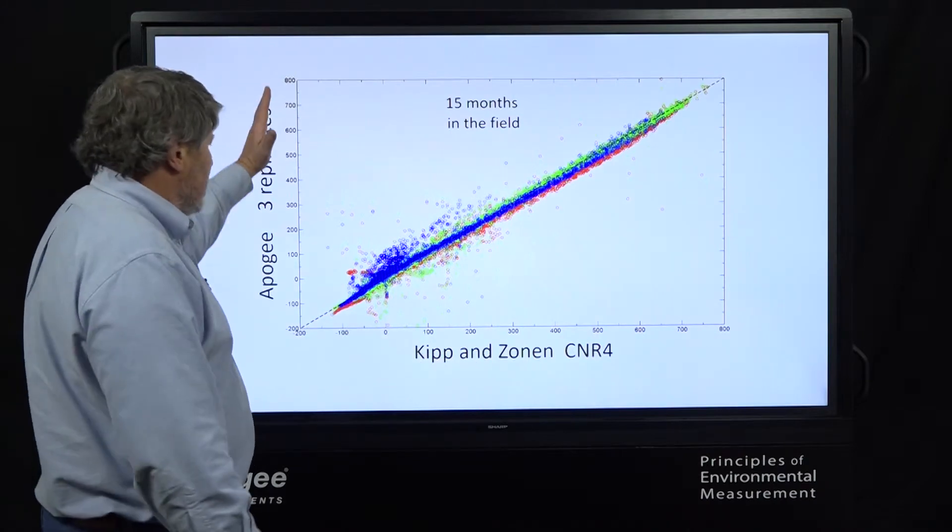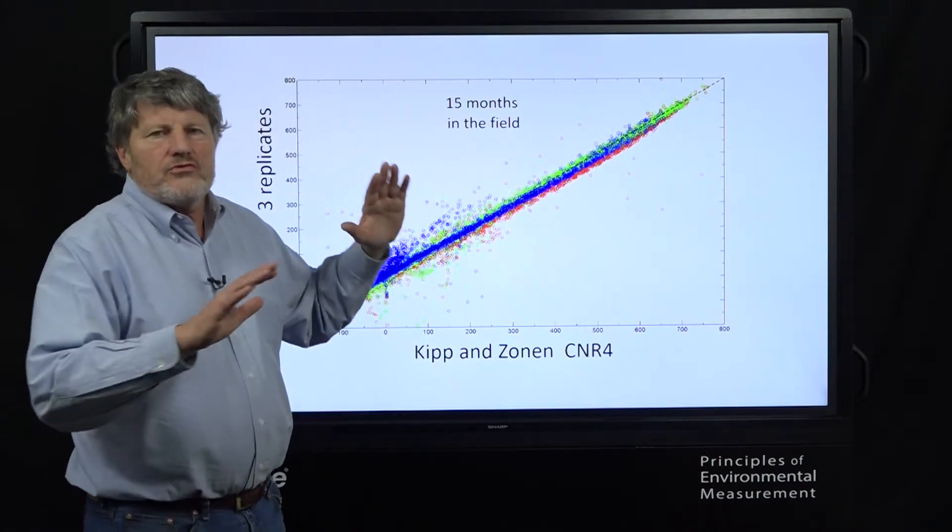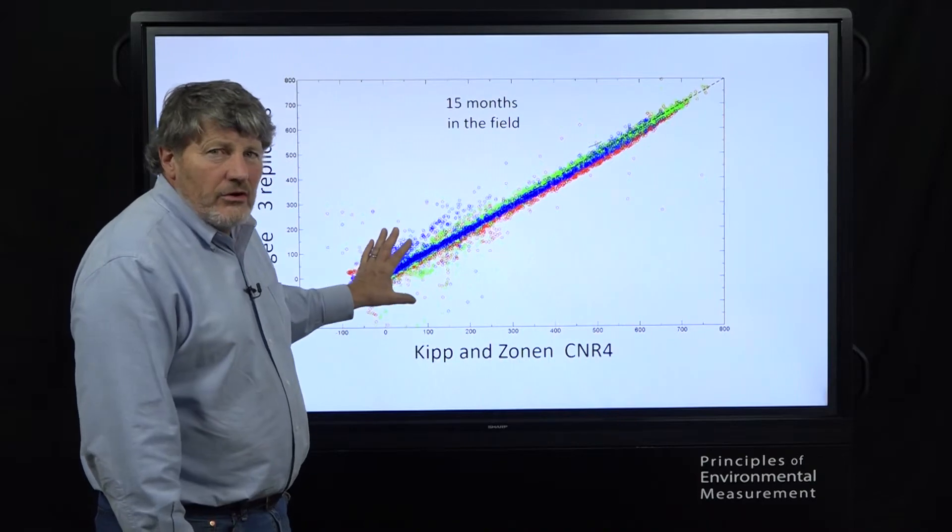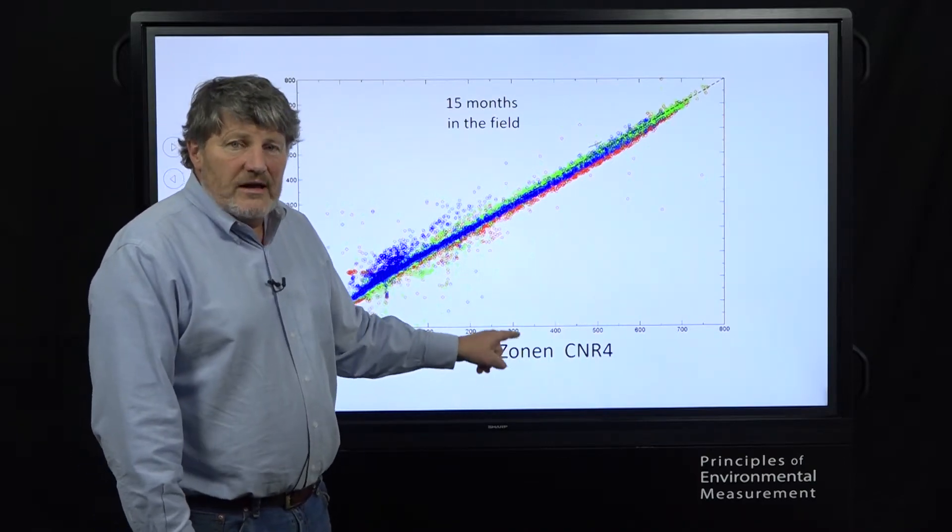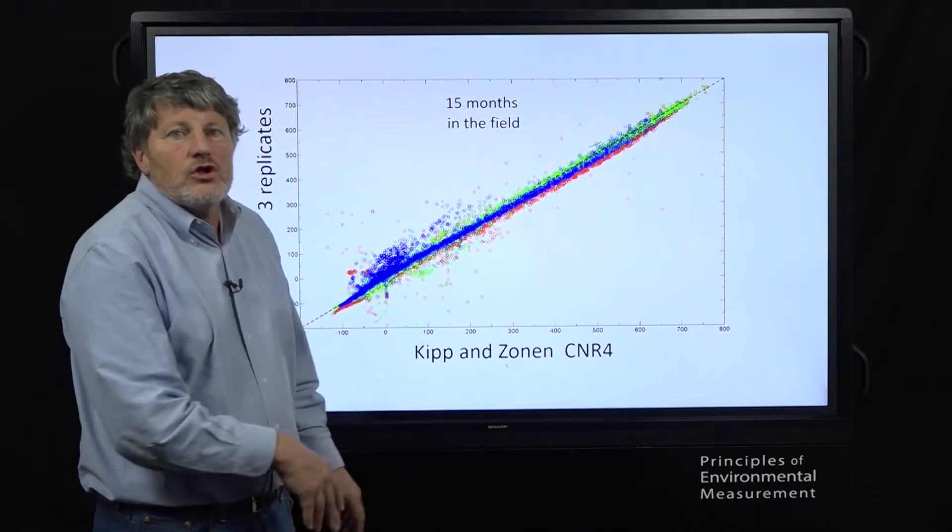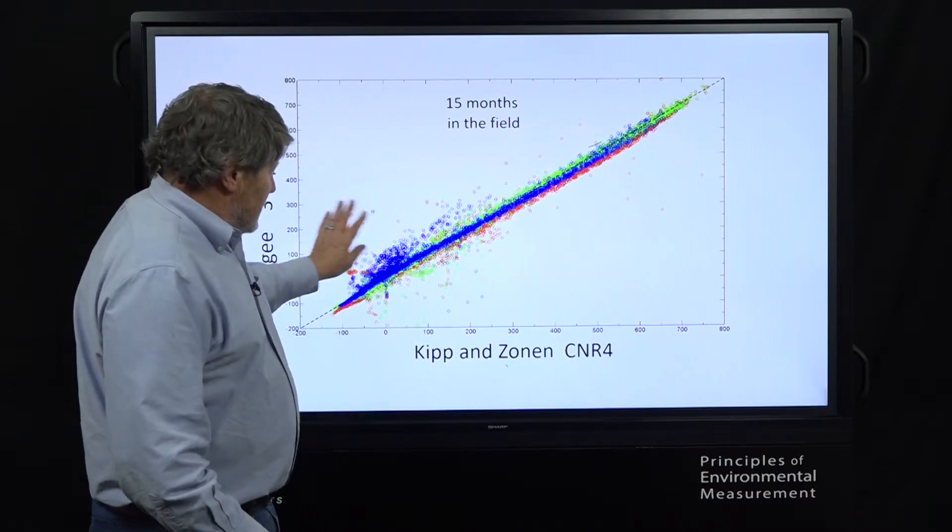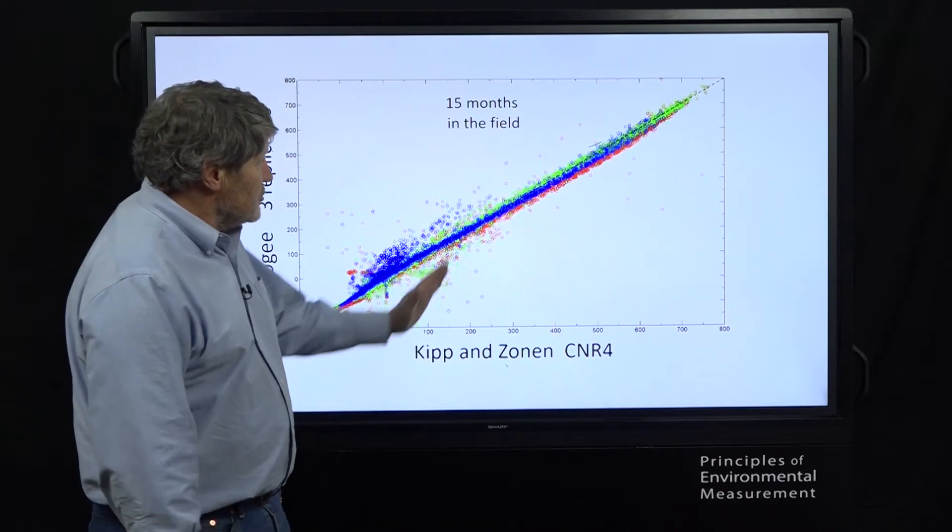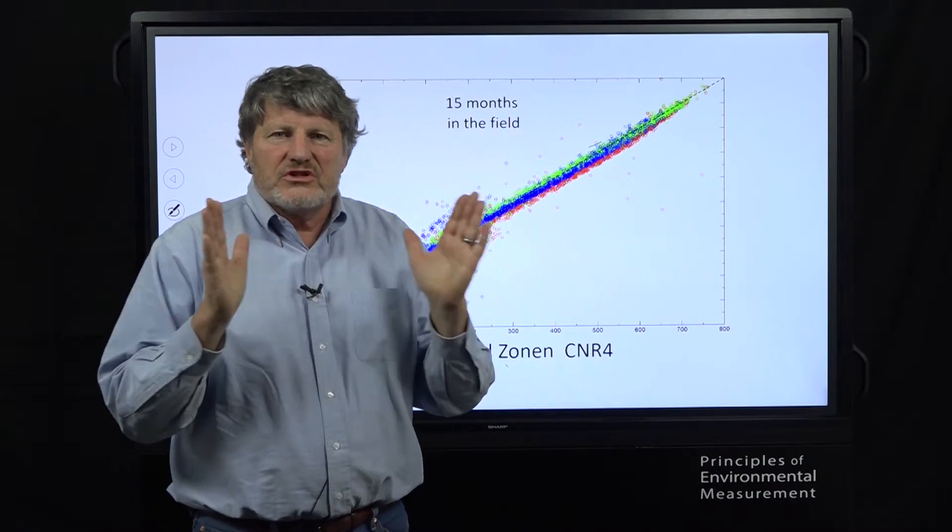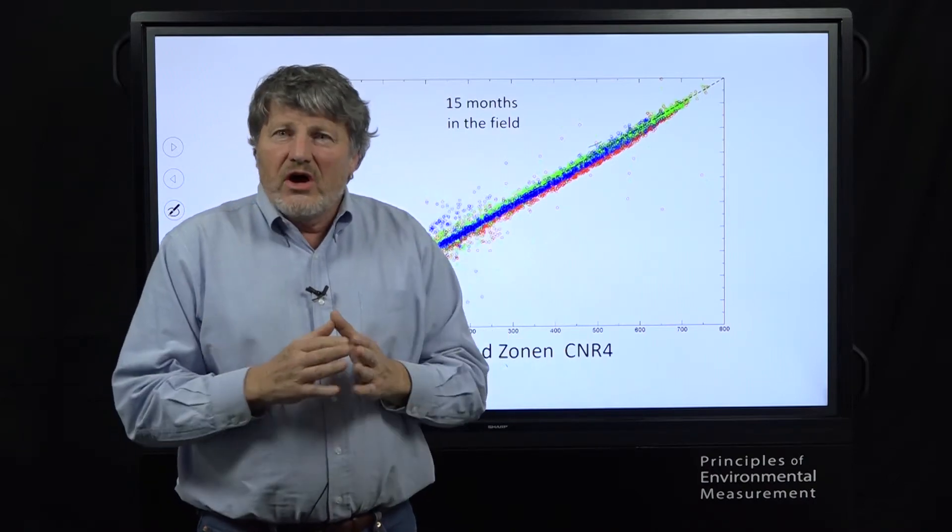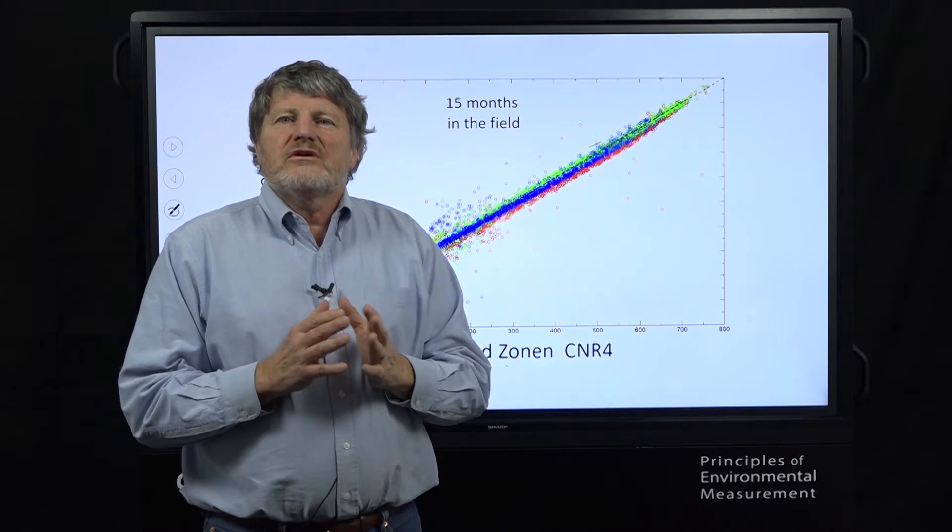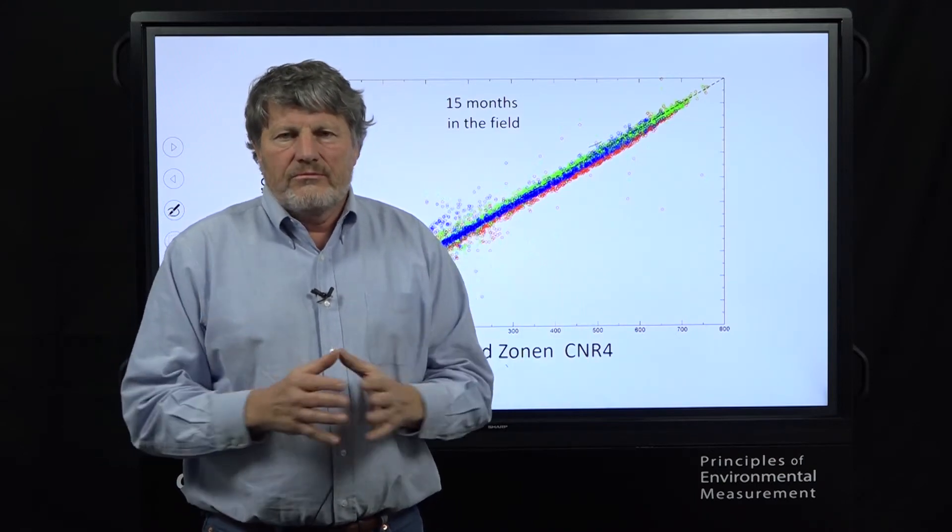Here's the reference, CNR4. Here's the three replicate Apogees. We were thrilled to see this tight line here. If you look closely at this, you can see some scatter. The CNR4 was not heated and ventilated, so there was days with dew which caused that to read low. So some of these data in here are caused by problems with the reference, not by the Apogees. These high radiation days where there was no dew and all three replicate instruments lined up beautifully. That's what we've done to make this accurate for the user is refine and refine and refine. Not only is it good out of the box, it's stable over many years.